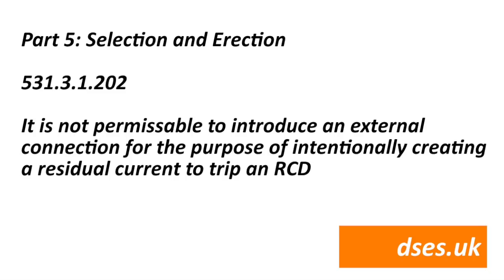Regulation 531.3.1.202 states it is not permissible to introduce an external connection for the purpose of intentionally creating a residual current to trip an RCD. This does not mean you can't use your tester to verify RCD times, but it does mean that if you're working on a circuit and want the RCD off, it's not acceptable to intentionally join a live line or neutral to earth to force it to trip. The point is that RCDs as electromechanical devices don't last forever, so forcing a fault current through one unnecessarily may reduce its life.